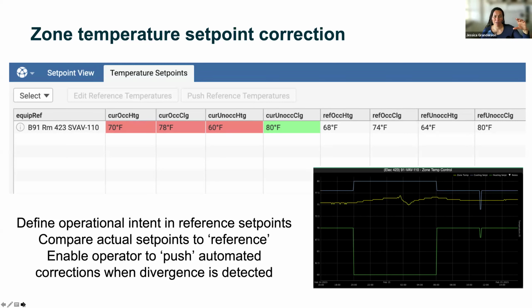Here I'm showing a screen grab. The red shows cases where the heating and cooling occupied and unoccupied set points are different from what the management team has defined as standard. Green means we're good, like an unoccupied cooling set point of 80, that was fine. Those reference operational intents can be compared to the actual. And then, if you can see my mouse, it's a little gray here, you can push reference temperatures back out to those zones that have diverged from policy.